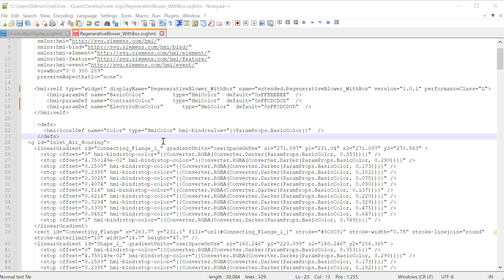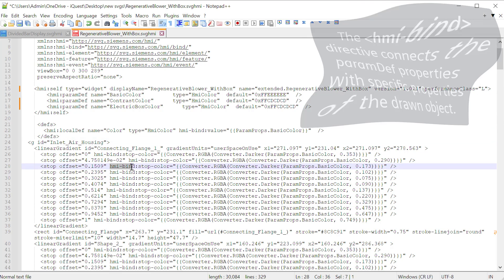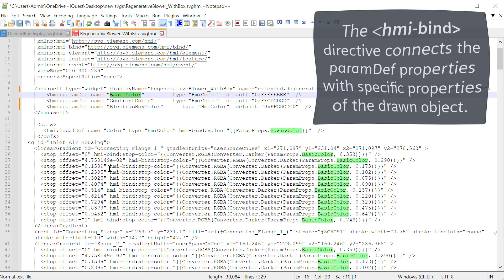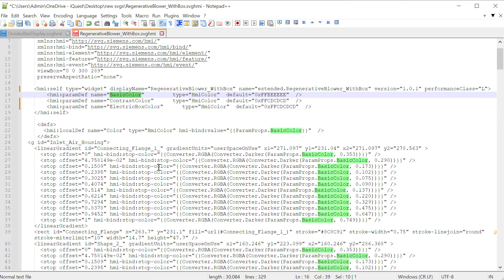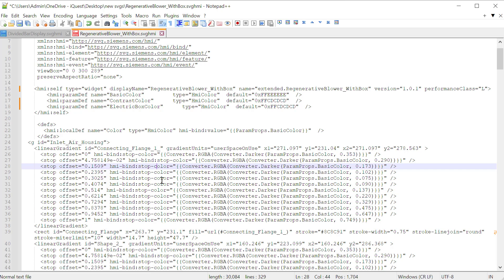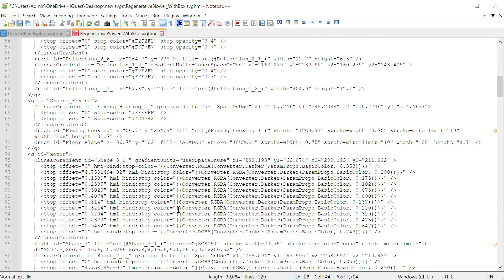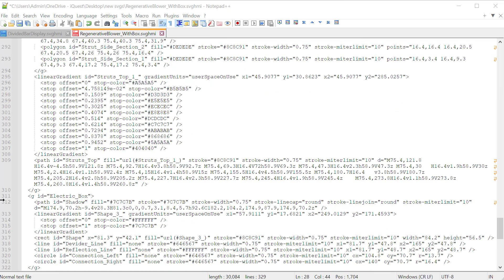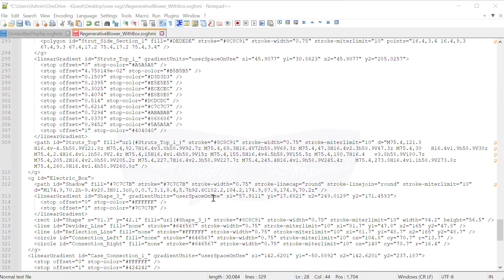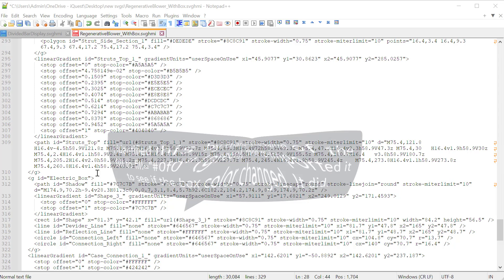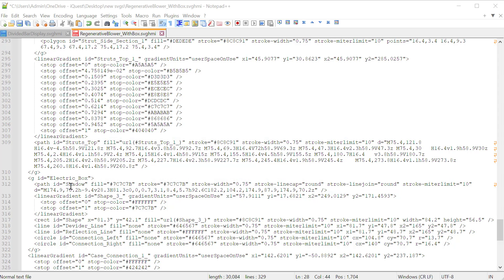So the first thing we have to do is find out in the drawing code where our electric box is. And we know that it is not dynamic because it didn't change color. So the first thing I'm going to show you is that the HMI bind directive, this is how we tie these properties up to the properties interface. So all of these objects that are using HMI bind, this particular one is just using the basic color and creating a gradient for our connecting flange. So we know that this is not it. And there's a lot of code here, but don't let it throw you. And we're going to come down to line 311 electric box. There is no HMI bind directive in here. So I'm pretty sure that this is it.